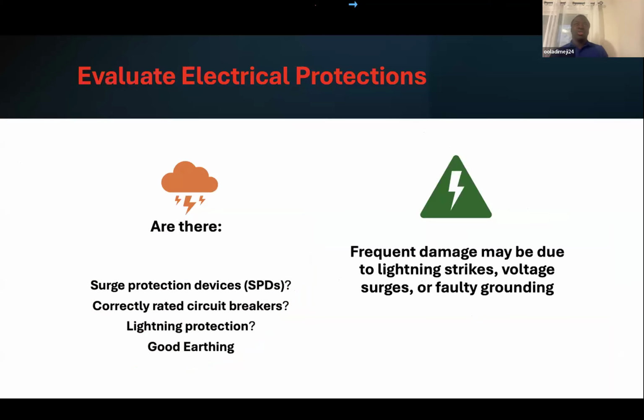Then you also need to evaluate electrical protections. Are there protection devices, the SPDs, correctly rated circuit breakers, lightning protection, good earthing? Frequent damage may be due to lightning strikes, voltage surge, and fault grounding. So you want to be sure that you have the right protection for your system.